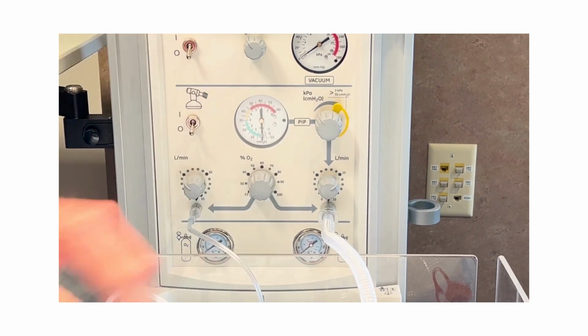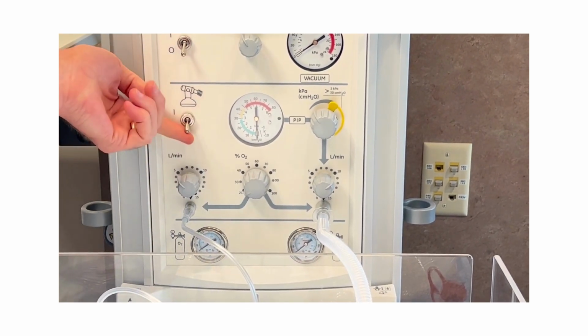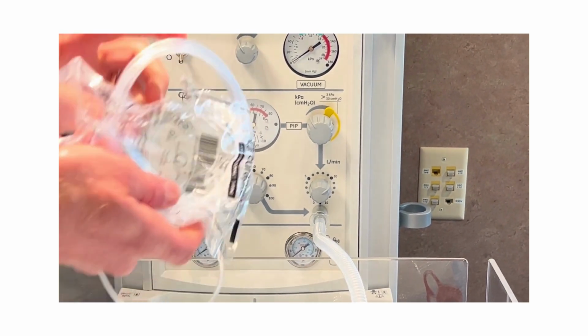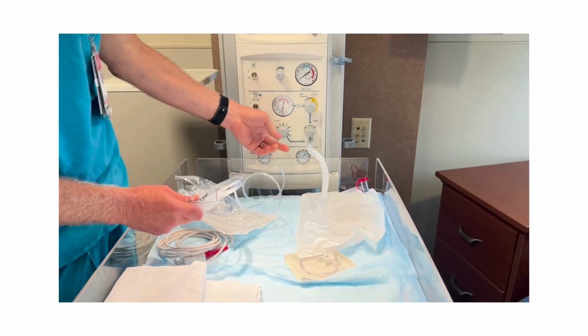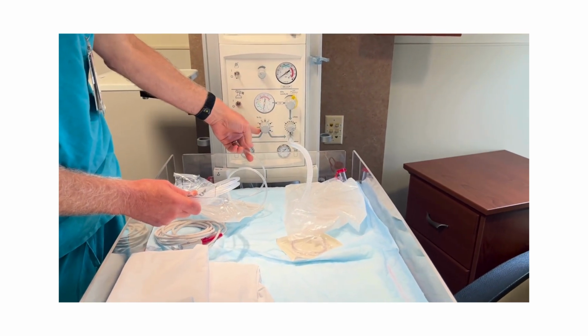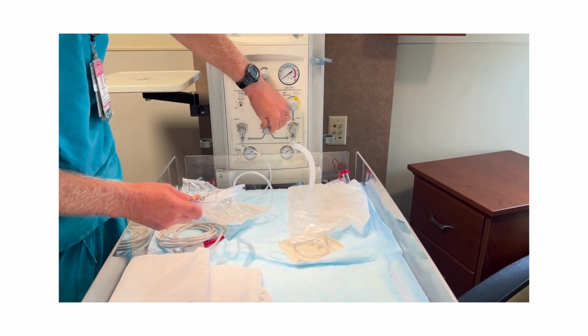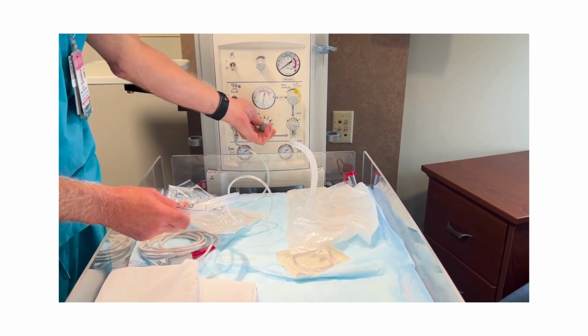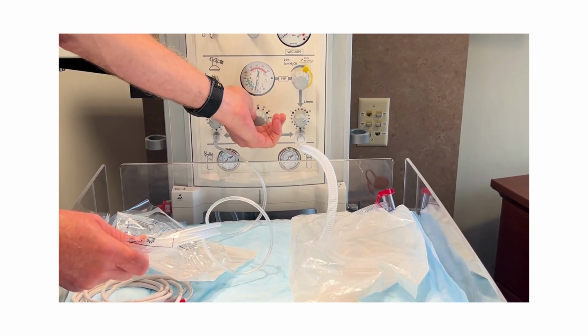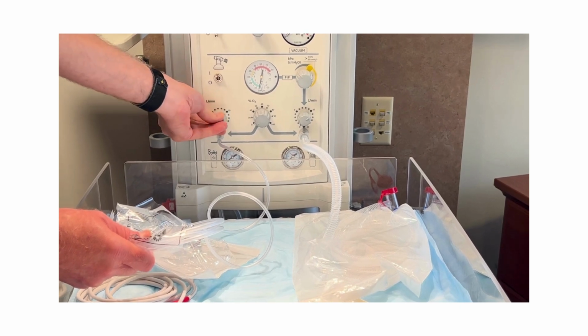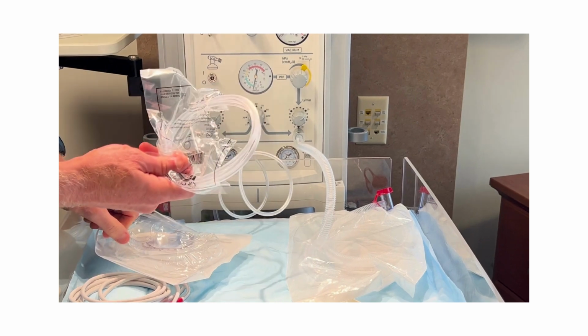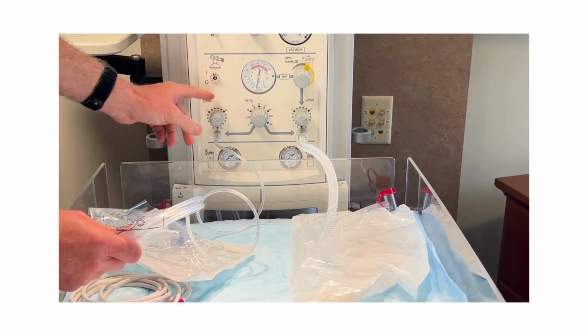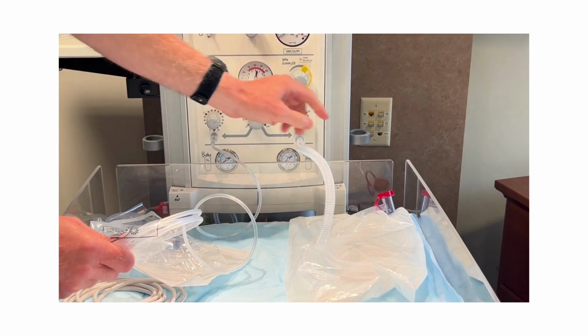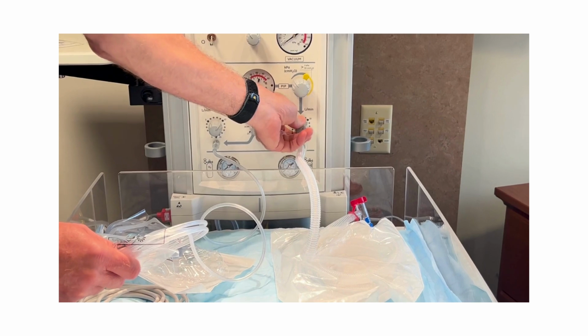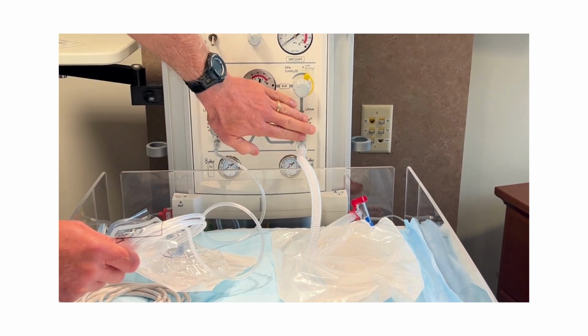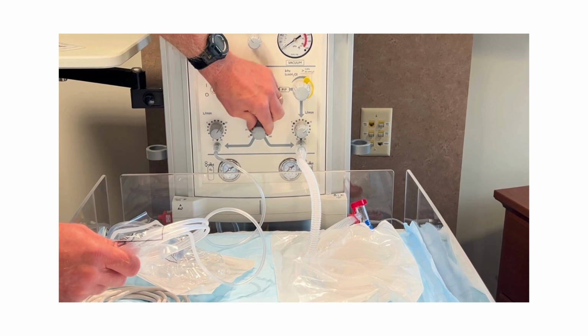But if you're giving a baby blow-by who needs oxygen, and you turn your gas on to give them blow-by, you always want to make sure you're giving oxygen if they need oxygen. Otherwise, you're just blowing air if you leave that on 21%. So this is to give blow-by oxygen at whatever percentage you need. Usually I would run it at 10 liters per minute for blow-by, as NRP recommends. And your flow meter for your Neopuff, you want to run that at 10 liters. So it's easy to just remember 10 and 10, and then whatever you need on the blender for oxygen.